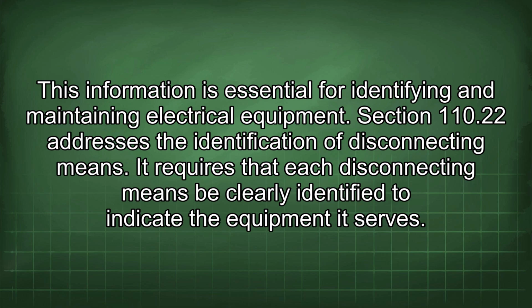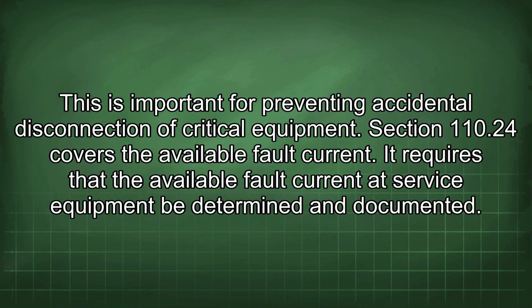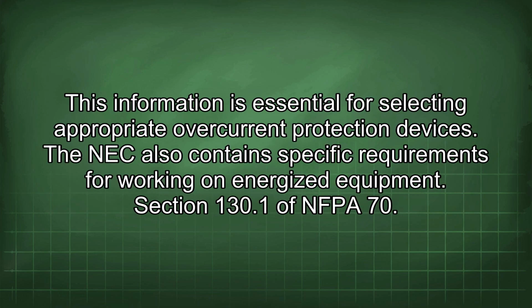Section 110.22 addresses the identification of disconnecting means. It requires that each disconnecting means be clearly identified to indicate the equipment it serves. This is important for preventing accidental disconnection of critical equipment. Section 110.24 covers the available fault current. It requires that the available fault current at service equipment be determined and documented. This information is essential for selecting appropriate overcurrent protection devices.